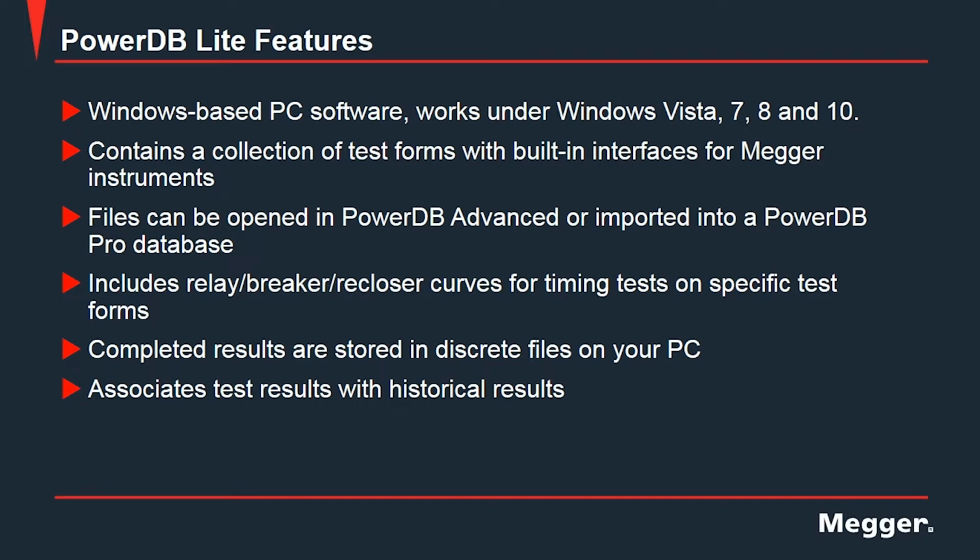It contains a collection of test forms with built-in interfaces for the Megger instrument, and the files can also be opened with PowerDB Advanced, or they can be imported into a PowerDB Pro database when you have the license for these versions. It includes relay curves or breaker and recloser curves for timing tests with specific test instruments.